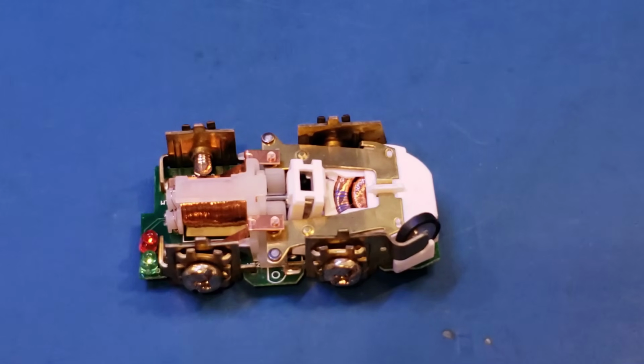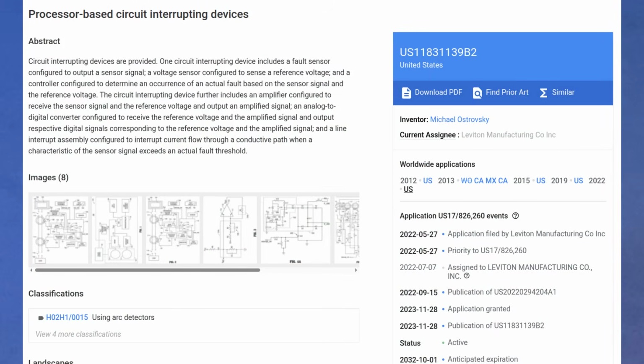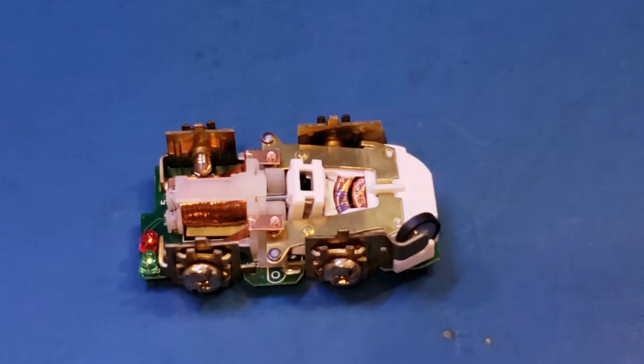Grounded neutral detection is somewhat more complicated, and there are a few methods for doing this. Again, in this Leviton GFCI, there is another patent covering the specific method used in this device. If you're interested, you can read the patent. But to dumb it down, the grounded neutral detection circuitry would inject a high-frequency signal into the neutral and then detect the signal from the return path through ground. And because the characteristics would be different depending on where the ground and neutral are connected together, for example, the inductance of the loop would decrease if the short occurs closer to the socket versus the junction box. Anyway, from a high level, the circuit is tuned to pick up the altered amplitude and phase response of the injected signal and trigger the grounded neutral fault protection, again, tripping the GFCI.